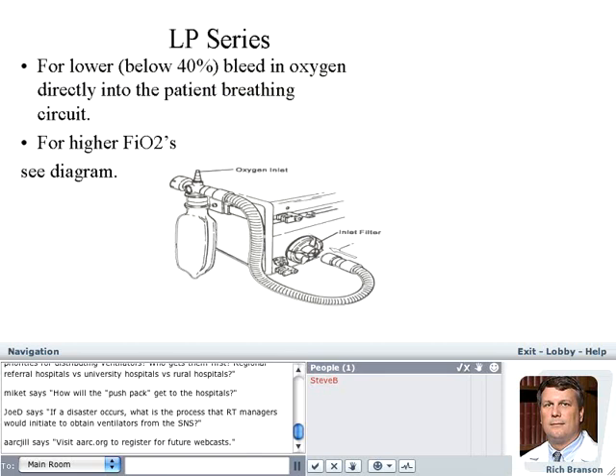The other issue about the LP10 is the bleed-in. It comes with two oxygen systems. One of the systems is shown in the picture here. The other one's just an elbow that goes on the outlet of the ventilator, and that's what you use if you want to have FiO2s below 40%. And realize that for any given oxygen flow, the FiO2 you deliver to the patient will depend on the respiratory rate and the tidal volume, so the total minute ventilation. And also remember that if you're bleeding gas into the inspiratory limb of the circuit, you'll also be augmenting tidal volume, so that's something you want to be aware of.